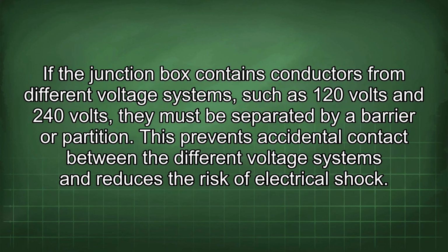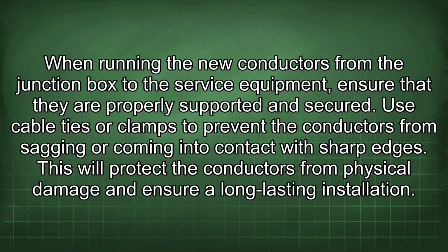If the junction box contains conductors from different voltage systems, such as 120 volts and 240 volts, they must be separated by a barrier or partition. This prevents accidental contact between the different voltage systems and reduces the risk of electrical shock. When running the new conductors from the junction box to the service equipment, ensure that they are properly supported and secured. Use cable ties or clamps to prevent the conductors from sagging or coming into contact with sharp edges. This will protect the conductors from physical damage and ensure a long-lasting installation.